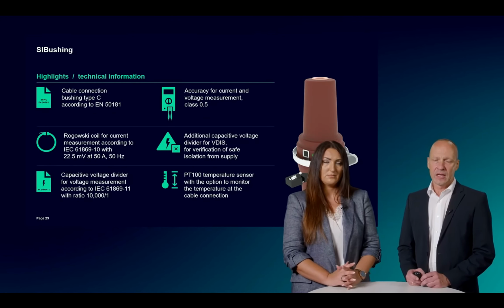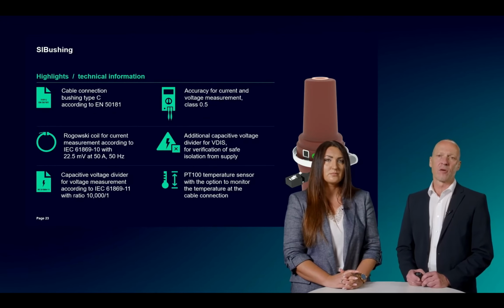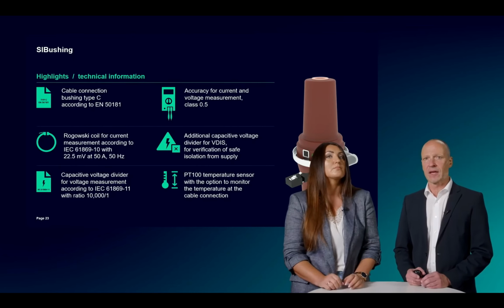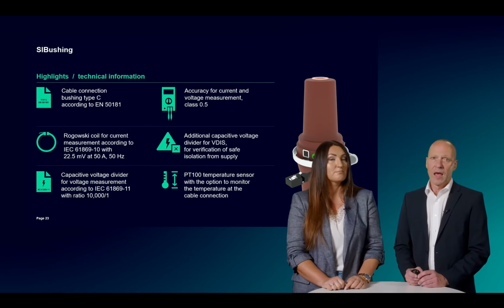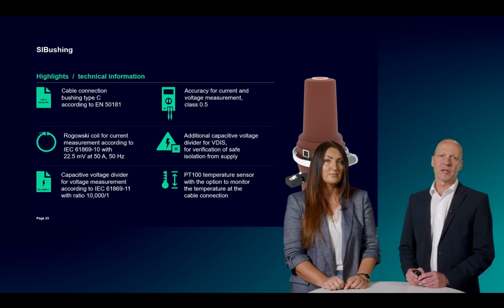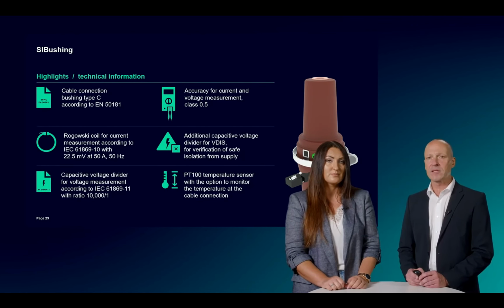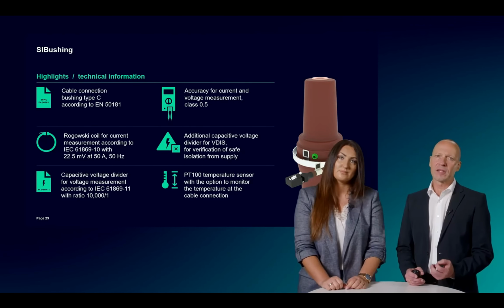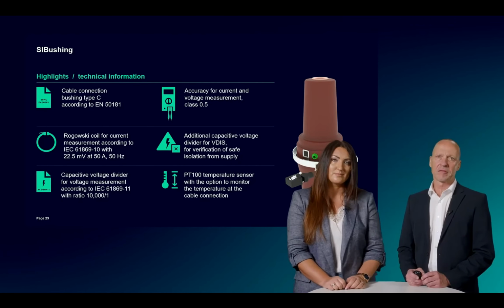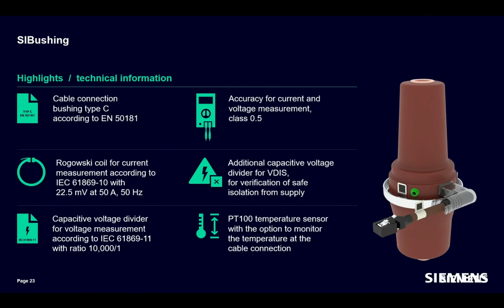This smart and intelligent bushing has an integrated Rogowski coil to measure the current and a capacitive divider to measure the voltage. Both are designed to the instrument transformer standard IEC 61869 and provide 22.5 mV at 50 Hz at 50 amps for the current measuring and a transformation ratio of 10,000 to 1 for the voltage measuring. The accuracy class is 0.5 for both voltage and current measuring.